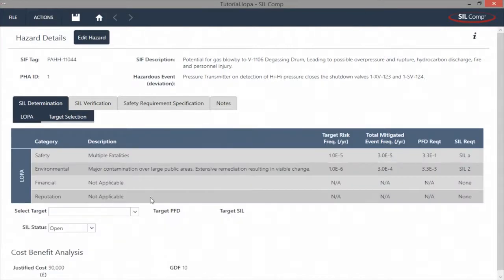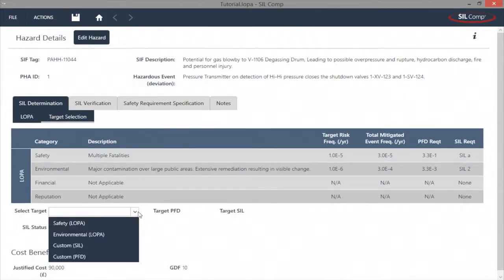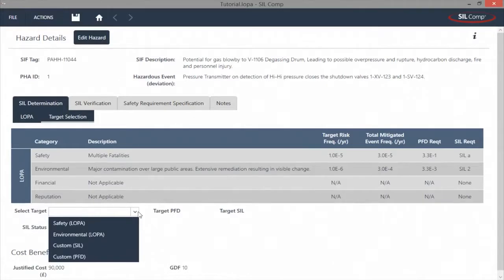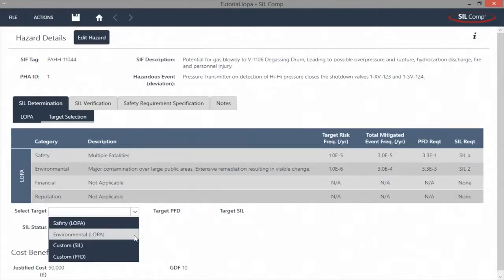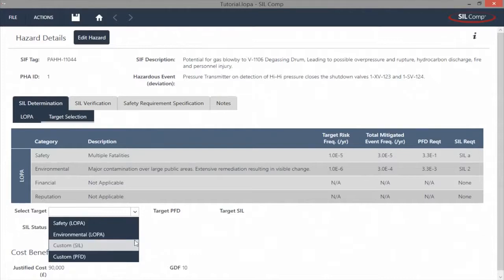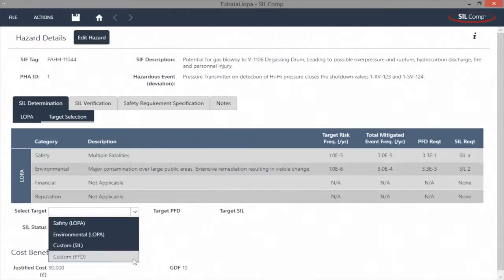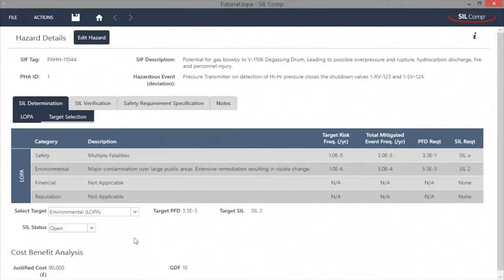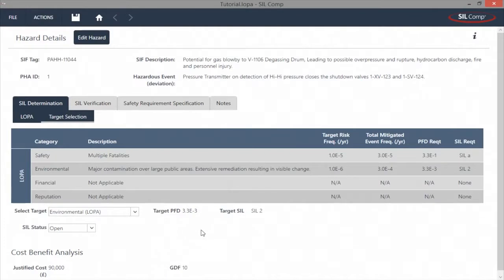In the context of LOPA, the SIL target can be set according to the relevant target risk that has been specified for each hazardous event for the specified risk category: safety risk, environmental risk, financial risk, or reputational risk. The SIL and PFD that have been determined from the LOPA can then be used for the SIL verification. If the SIL and PFD have already been determined prior to using SILCOMP, this can be input immediately into the SIL verification module. The cost-benefit analysis module, for use as part of the as-low-as-reasonably-practical demonstration, that is, the ALARP demonstration, automatically incorporates data from the SIL determination and SIL verification modules within SILCOMP.